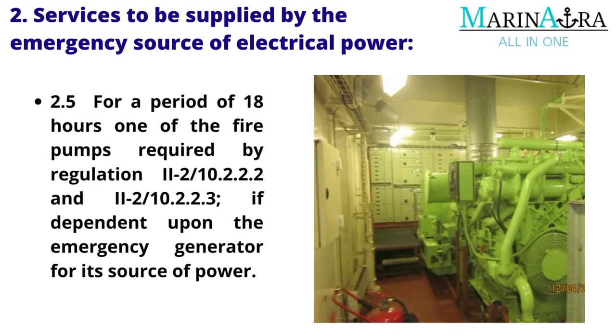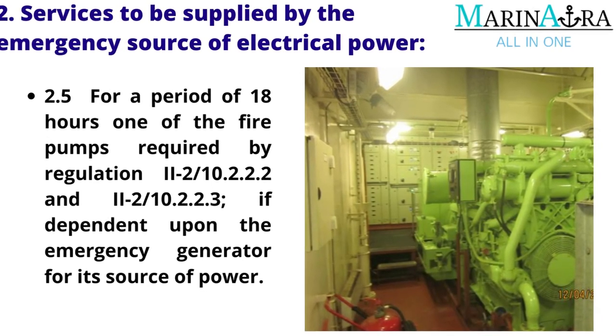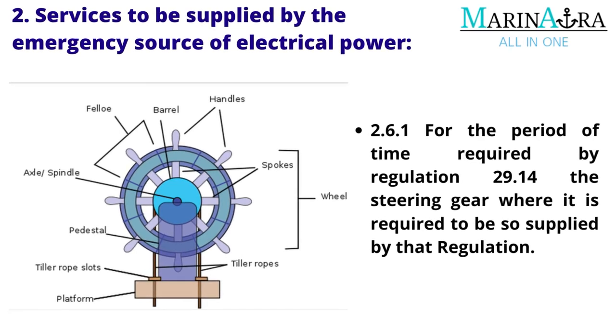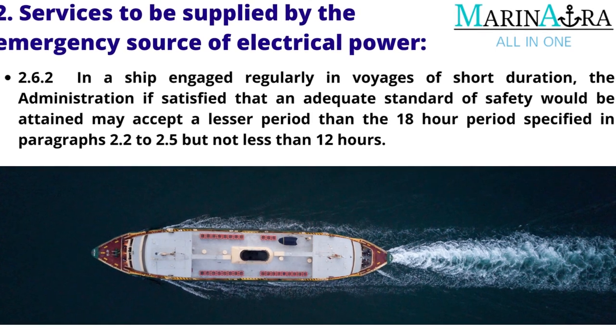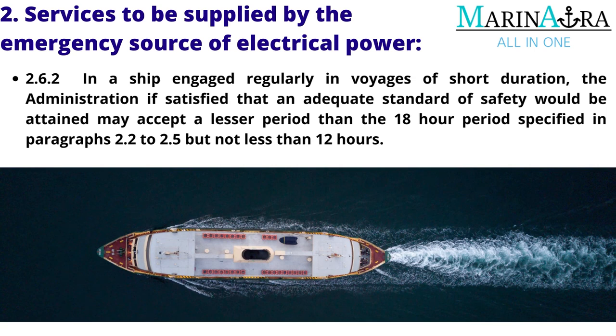For a period of 18 hours: one of the fire pumps required by Regulation II-2/10.2.2.2 and II-2/10.2.2.3, if dependent upon the emergency generator for its source of power. For the period of time required by Regulation 29.1 for the steering gear, where it is required to be so supplied by that regulation. In a ship engaged regularly in voyages of short duration, the administration, if satisfied that an adequate standard of safety would be attained, may accept a lesser period than the 18-hour periods specified in paragraphs 2.2 to 2.5, but not less than 12 hours.